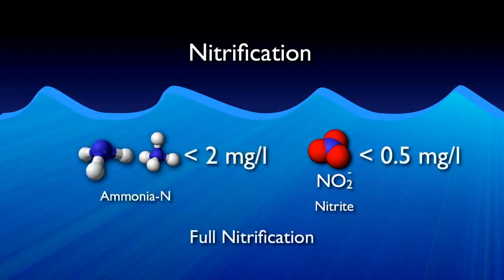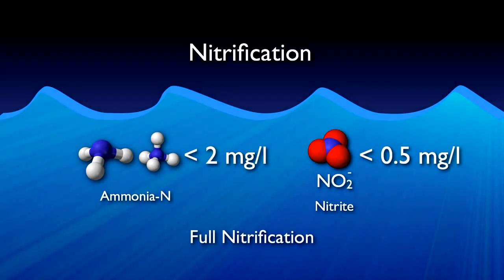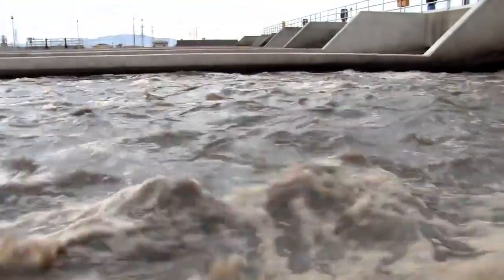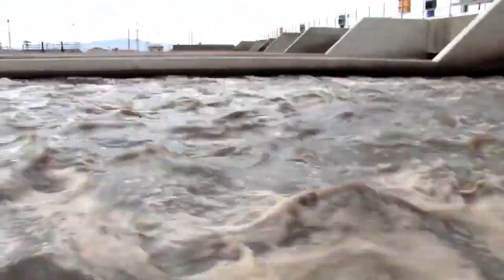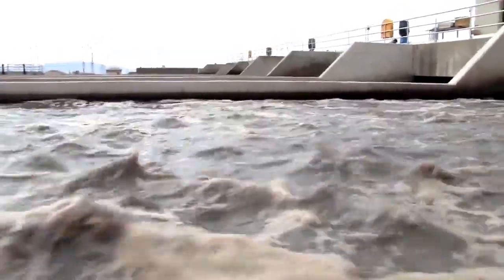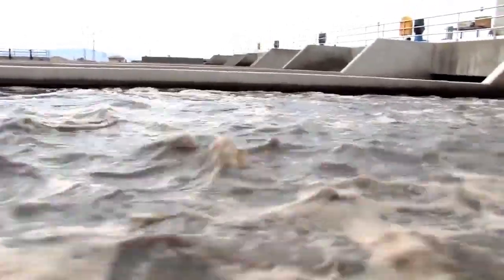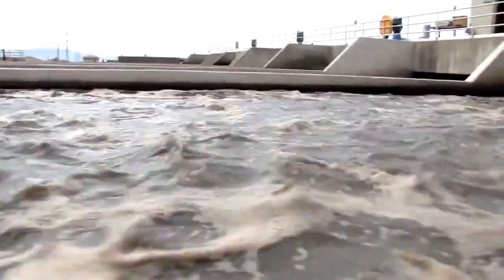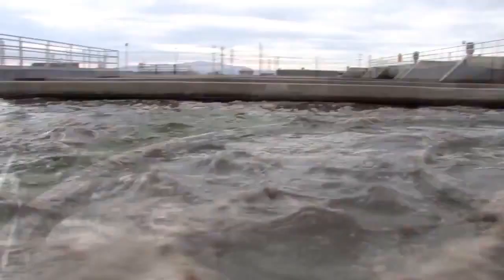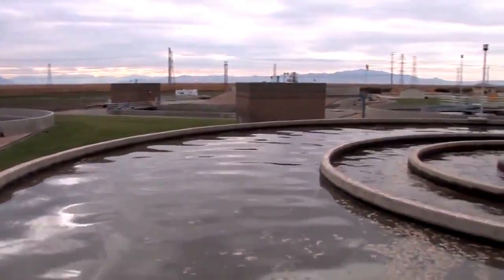Full nitrification is observed when ammonia concentrations are reduced to less than 2 mg/L and nitrite concentrations to less than 0.5 mg/L. Nitrification is a very oxygen-hungry process. To remove one pound of BOD, 1.2 pounds of oxygen are required; however, to reduce one pound of ammonia to nitrate, 4.6 pounds of oxygen are required.